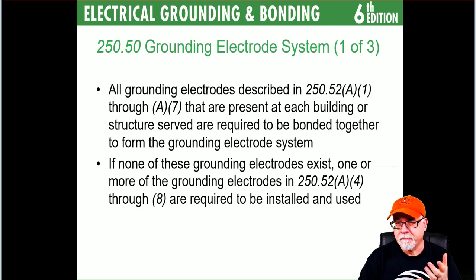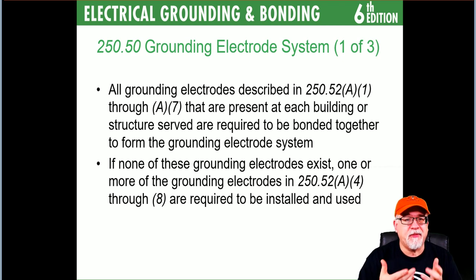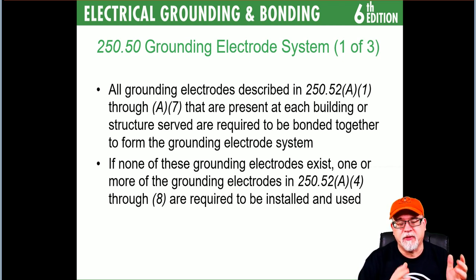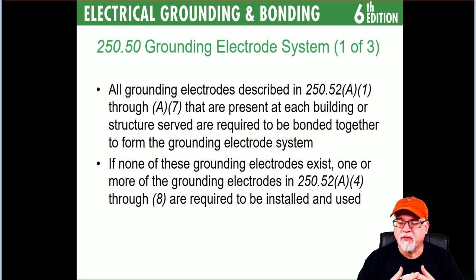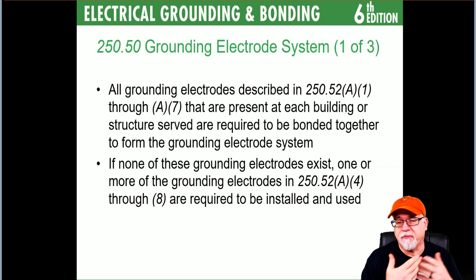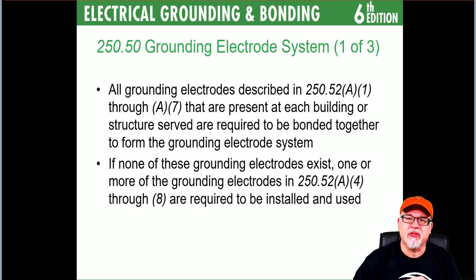The key difference is that 250.52(A)(1), (A)(2), and (A)(3) are typically things inherent to construction — concrete encased electrodes designed in the footer, or a water pipe in contact with 10 feet of earth. However, if they are not present at the building, then you have to establish one using 250.52(A)(4) through (A)(8).